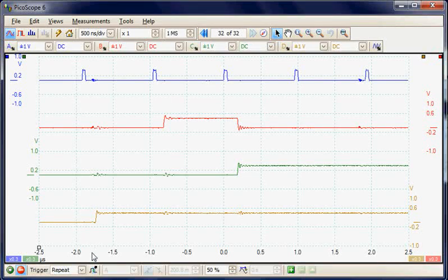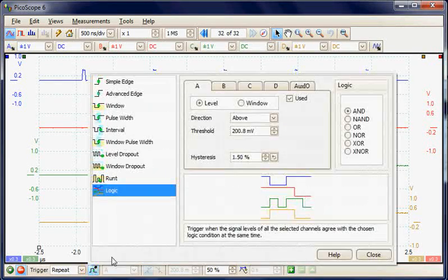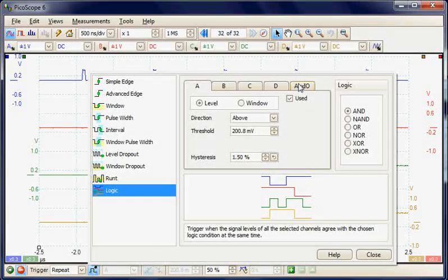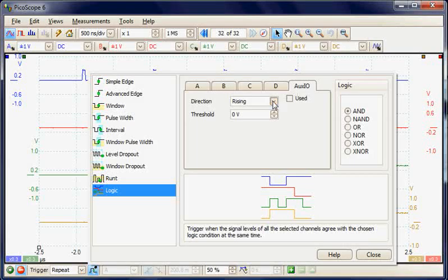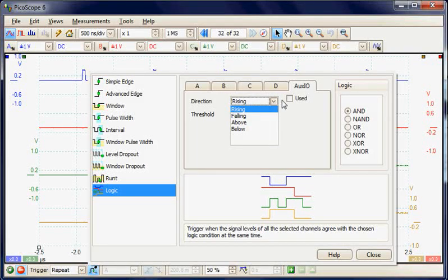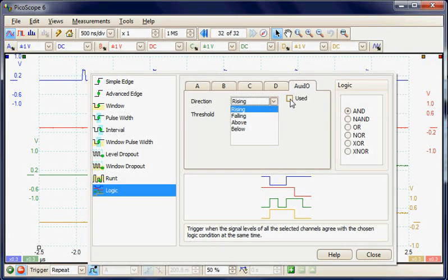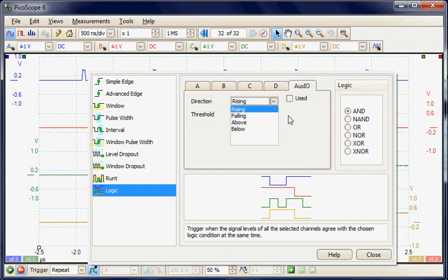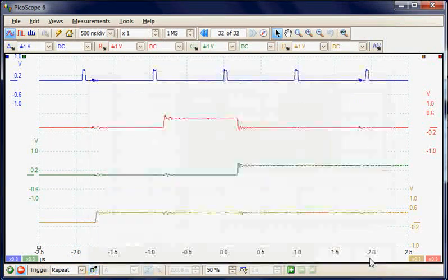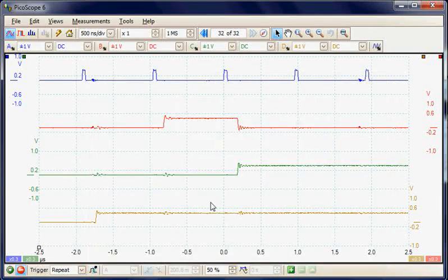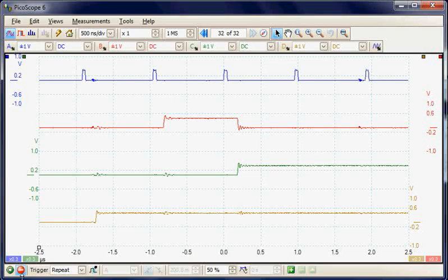It is possible to have a fifth channel using the auxiliary IO input and again we can select a high or low condition and use it in the trigger condition. This fifth channel cannot be displayed but it would allow for a 5-bit trigger sequence to be acquired.